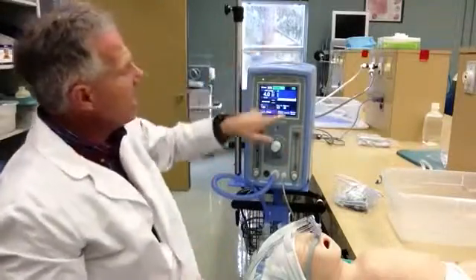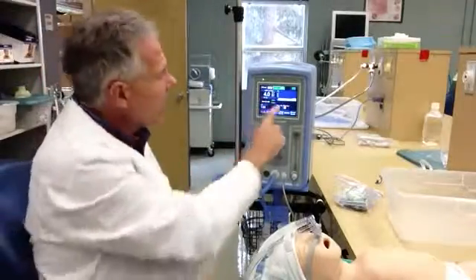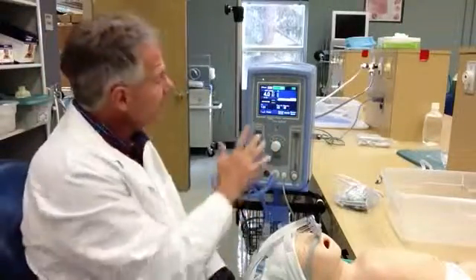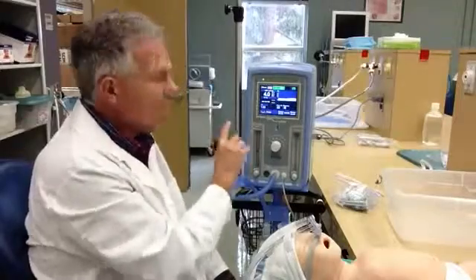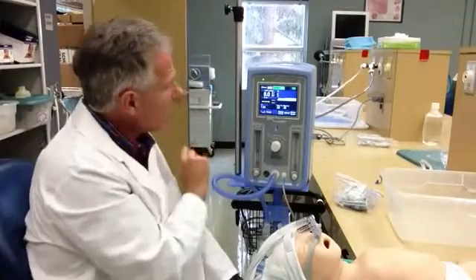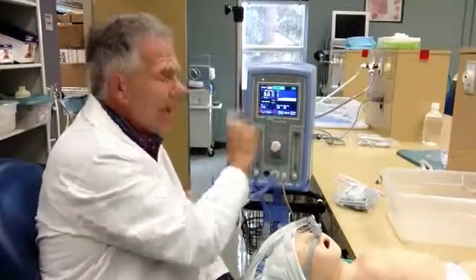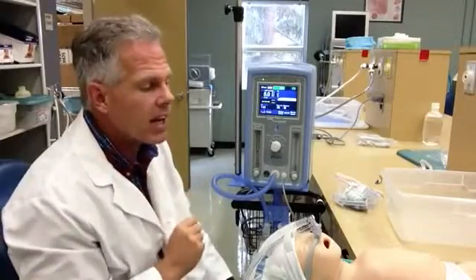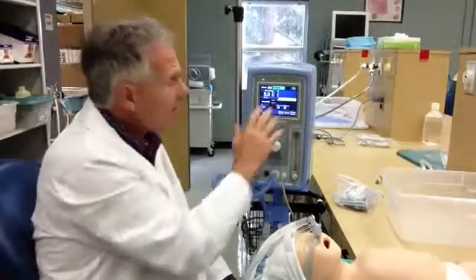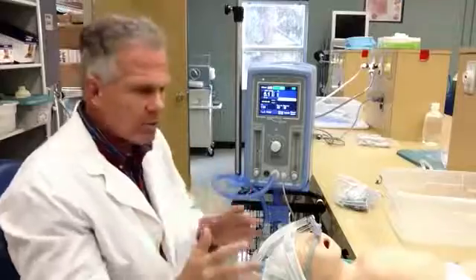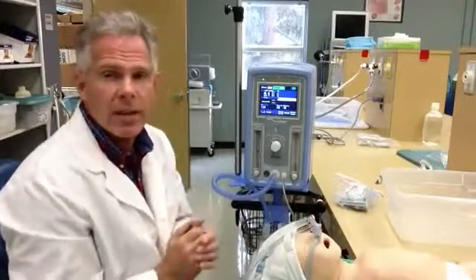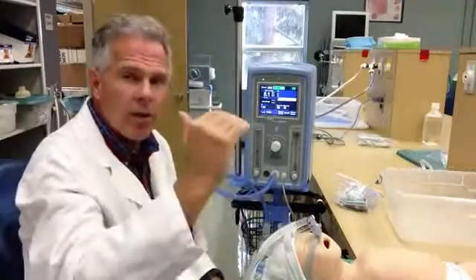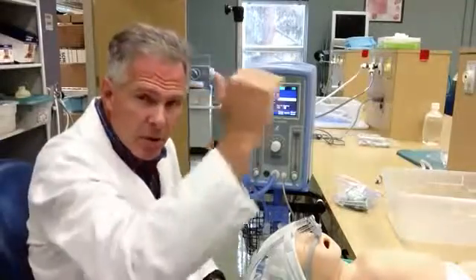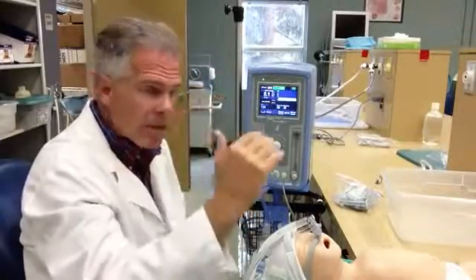and I click in my biphasic. And now if you watch your screen here, you can see that it's oscillating, giving me an I:E ratio of 1 to 2, shows me the I:E ratio, a rate of 40, and my T-high is 0.5 seconds. So right now it's giving biphasic ventilation. It's not responding to the patient's inspiratory efforts. It's just mechanically going from your CPAP to your high pressure, CPAP to your high pressure.